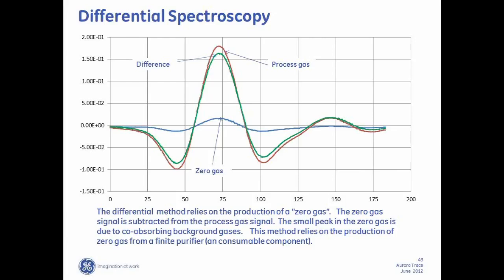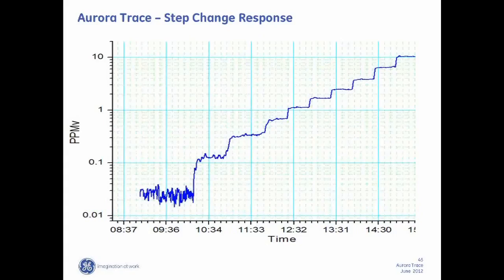And this is just data showing the response time of the Aurora-Trace as compared to a chilled mirror. Notice that it's on a logarithmic or an exponential scale on the y-axis, but these were 3 different units that dry down. One of them was at a slightly faster flow rate, and the T90 here is less than 2 minutes. So again, very fast response times as compared to other technologies. And those are just step changes on the Aurora.